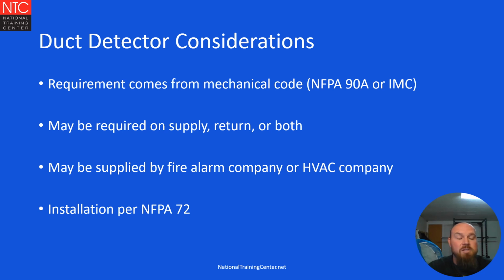Couple things to take into consideration. The requirements for when a duct detector is needed come from the mechanical codes, whether that's NFPA 90A or the IMC. They may be required to be on the supply, the return, or on both, depending on the code you're going with. Sometimes they're supplied by the fire alarm company, sometimes they're supplied by the HVAC company. However, whoever is supplying them, the installation does have to conform with NFPA 72.